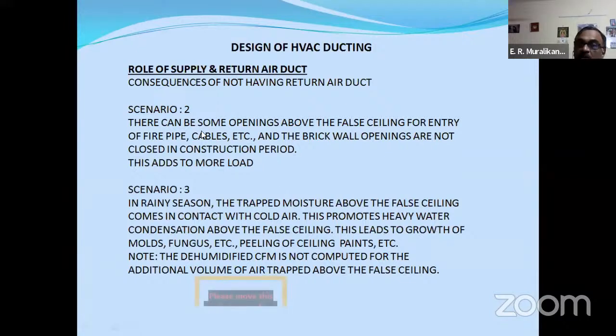Now, scenario 2: there can be some openings above the false ceiling, for entry of cables or fire pipes, etc. In this very common scenario, suppose on the same floor you have a washroom. Above the washroom, the wall will not be built. It will be stopped at the false ceiling only, say to save the brickwork of maybe 3 or 4 feet height. The entire duct is passing over the false ceiling, so this gap above the bathroom will be pulled by the air into the return duct. What will happen? This adds load again.